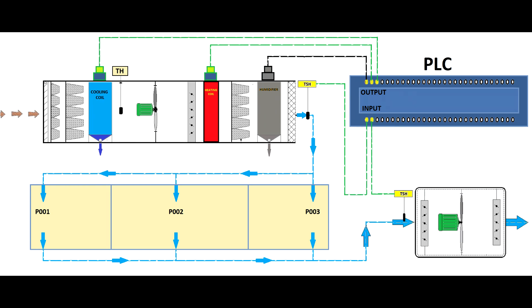Guys, let's talk about the mistake I told you about. This AHU, like you'll see in this video, we have two temperature and relative humidity probes fitted. One onto the supply duct, which is on the right hand side, in between the PLC and the AHU, it's marked with yellow, it's a TSH probe. And the other one which is on the extractor fan's duct on the right hand side to the bottom. Can you imagine, this system brings air from outside only, and sometimes outside the air can have a very fast increase in its moisture, or the temperature can drop very fast or it can raise very fast.